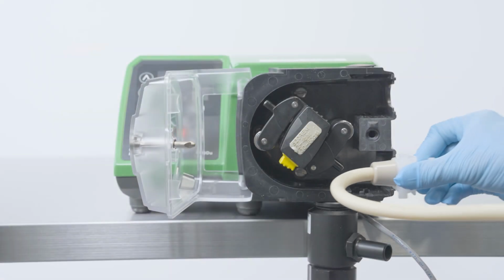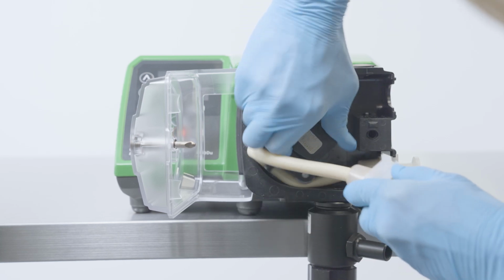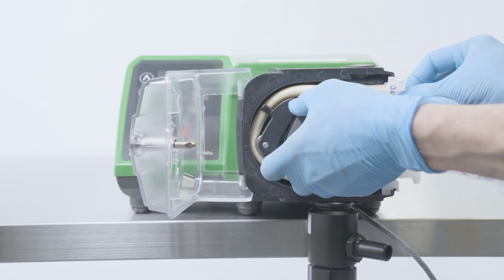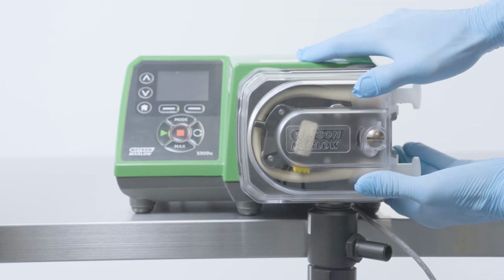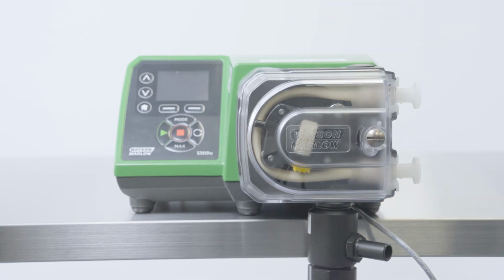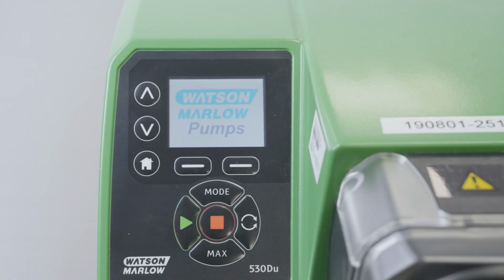To reinsert the element, slide the LoadSure connector into the guide at the bottom port. Push the tubing into the track whilst rotating the rotor clockwise. Close the guard, ensuring it clicks shut. Turn the pump on. If the leak detect screen still shows, you can reset this using the prompt.